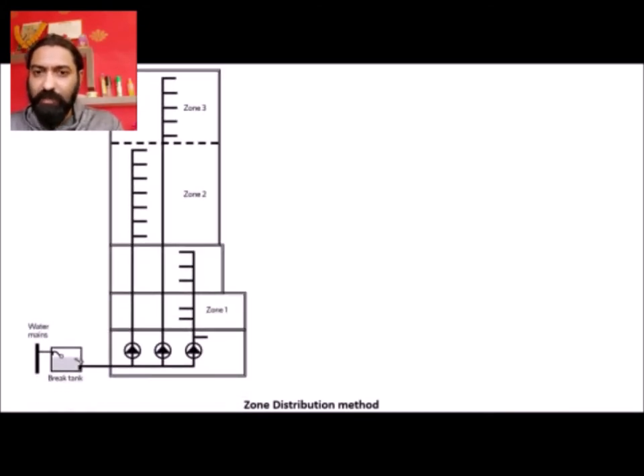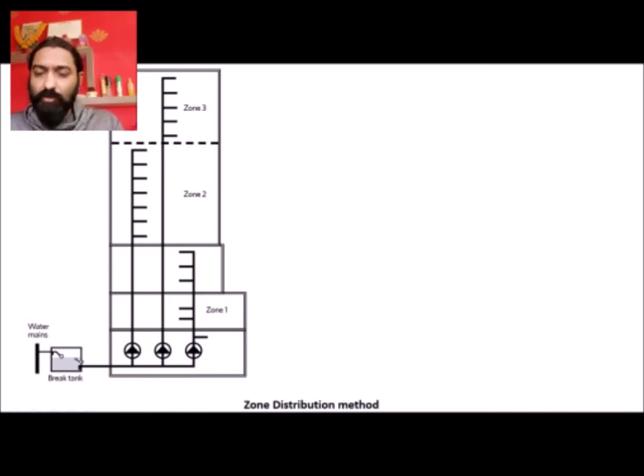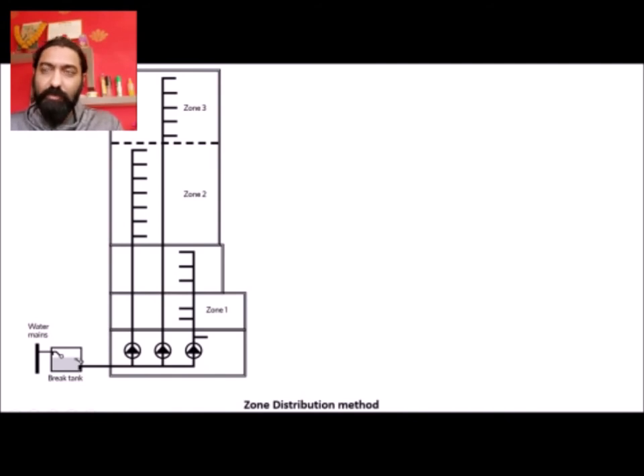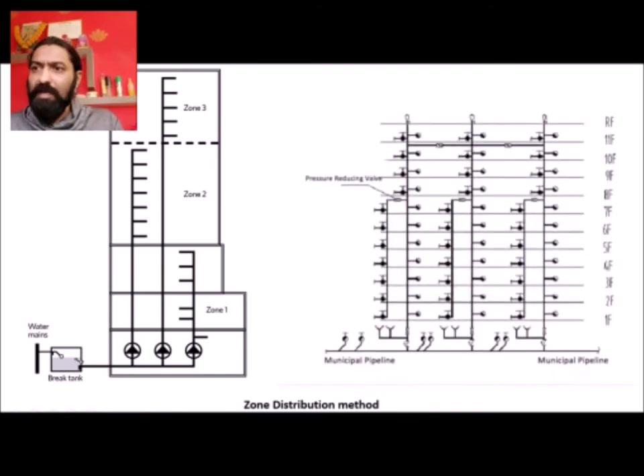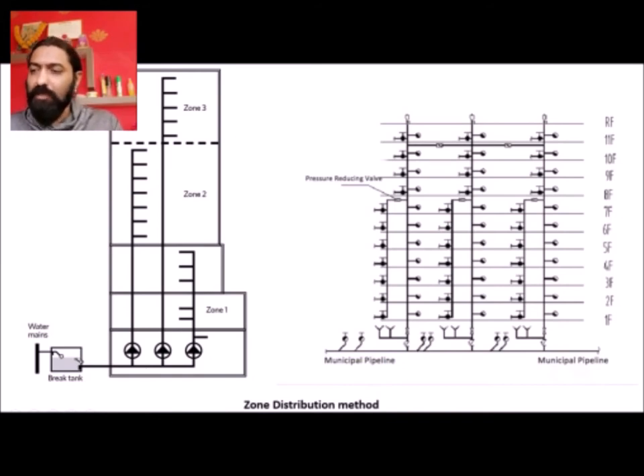In the first case, we use a pressure reducing valve. The zoning system means that for a building of 100 floors, instead of a single water storage tank at roof level, we provide 10 smaller tanks at various levels, dividing it into smaller zones. Previously, PRV methods were used; now the zoning method is most popularly used, dividing the building into multiple vertical zones, each with its own dedicated water storage tank.